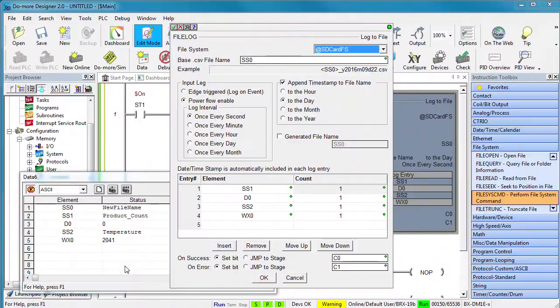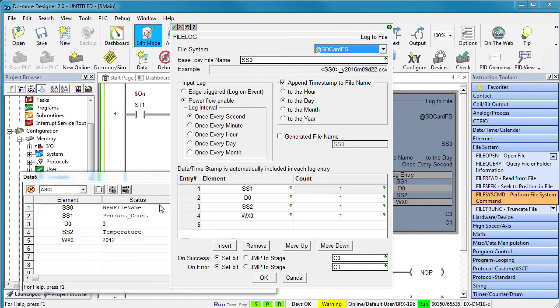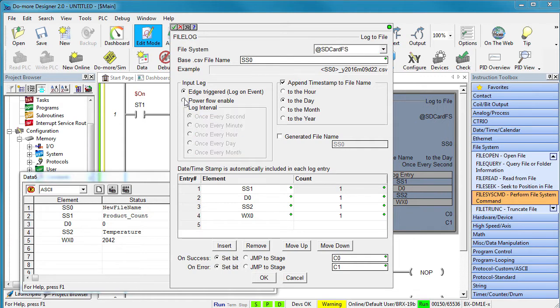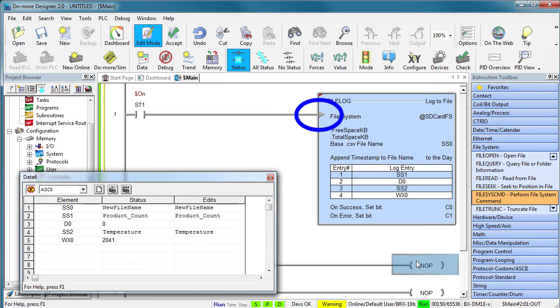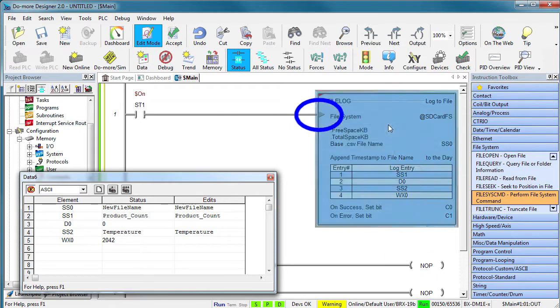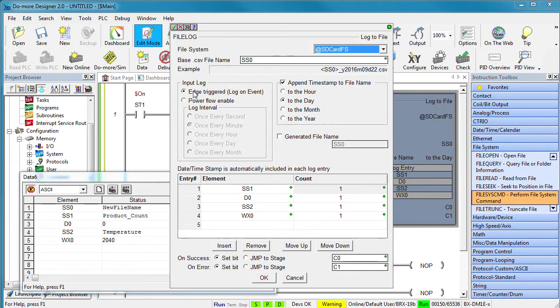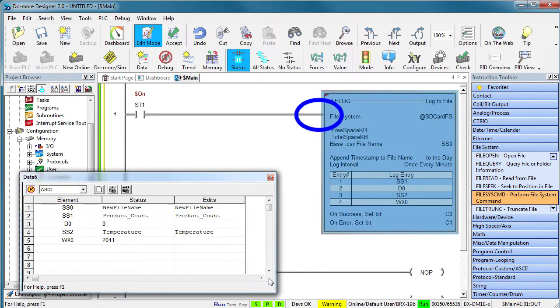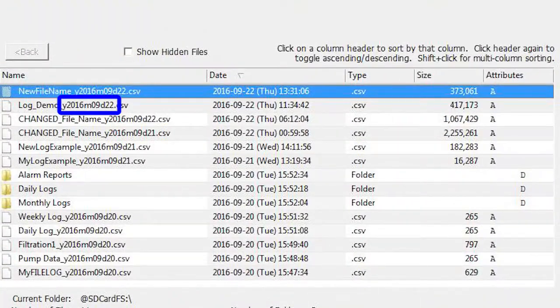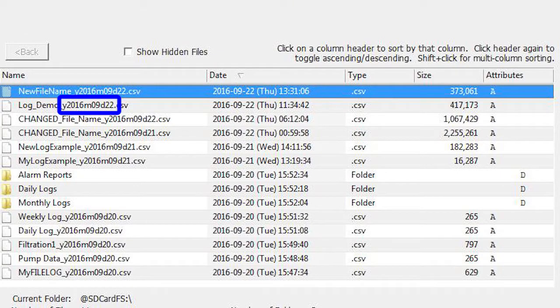We have been triggering our log based on a specific time period – but you can also trigger on any event. When you select that option, it just adds an edge triggered input to the instruction so you can trigger on anything you want. Undo that and now it just logs periodically as long as the power is applied. You have already seen the file name timestamp – that was this guy in our previous example. That's really handy.